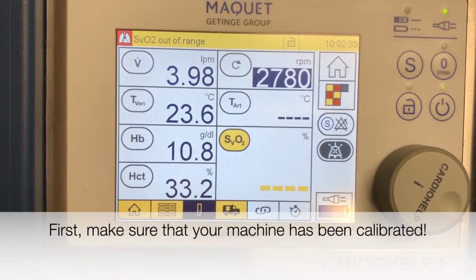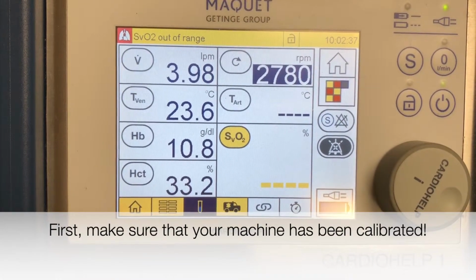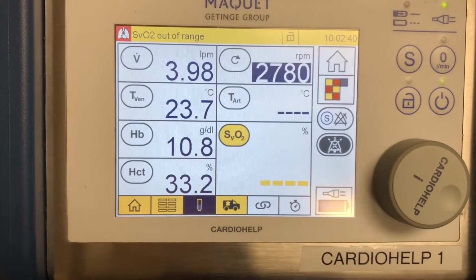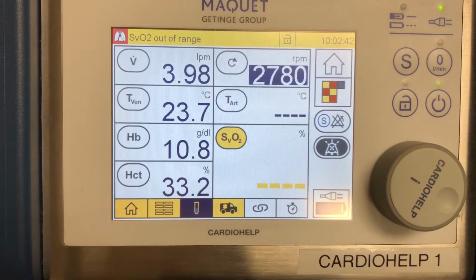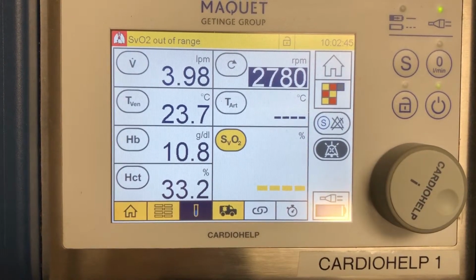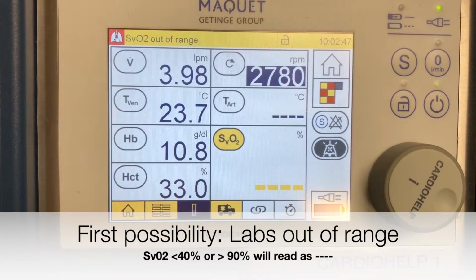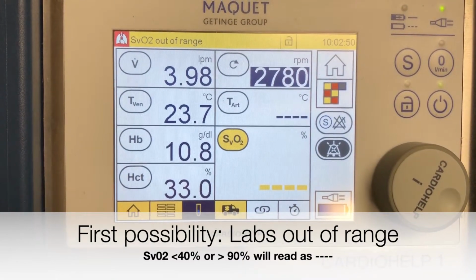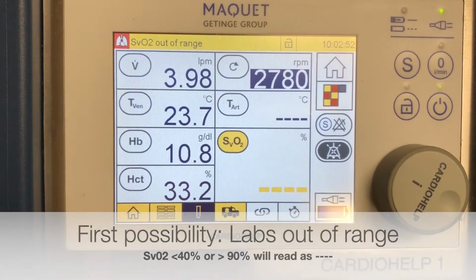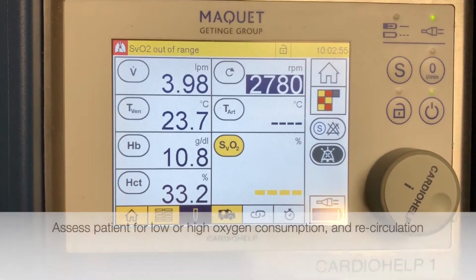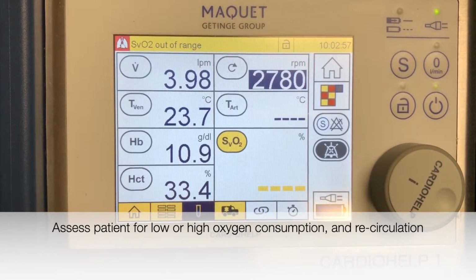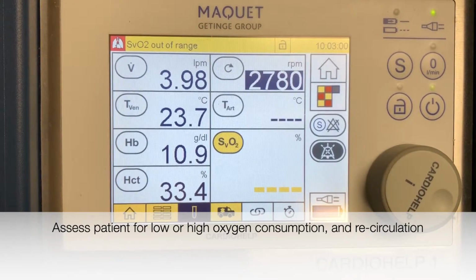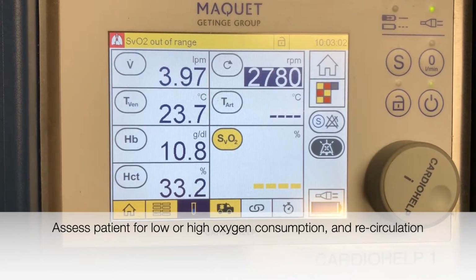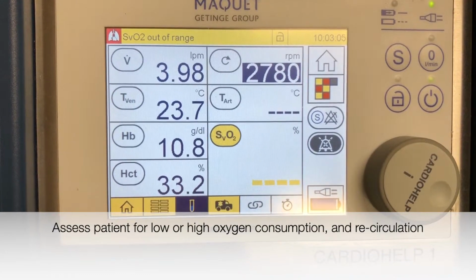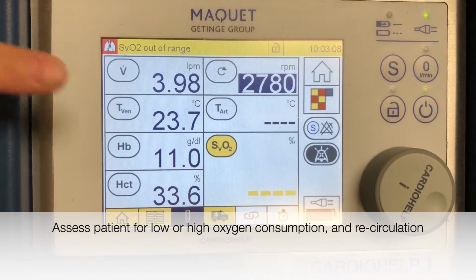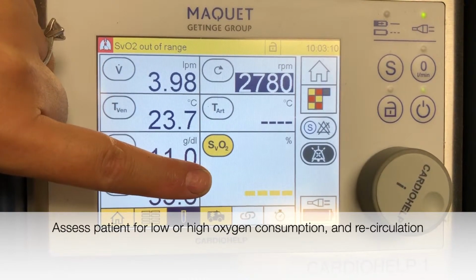You've already done your gases and you've already calibrated it. Everything was running fine and suddenly you see this. So a few things could be happening in this scenario. Number one, your values for that lab can be out of range. Any value below 40% or above 90% will dash out. It cannot read it. So if a patient for any reason desats so much that it drops below 40, or there are recirculation issues where the cannula is positioned in a way that it's just pulling whatever it's putting in, and your mixed venous starts going up over 90%, then you're going to have dashes because it cannot read those ranges.